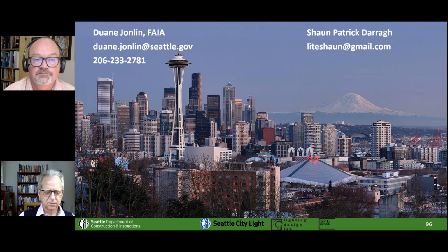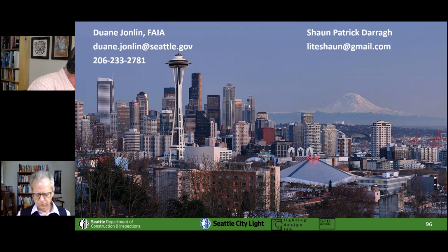Getting back to Jose, he had read an excerpt that any space under 300 square feet requires an occupancy sensor, and this was in relation to asking why electrical rooms don't need an occ sensor. Oh, electrical rooms are specifically exempted. There's an exception that says if you go back to the beginning of the lighting controls area, you'll see that overall exemption for them.